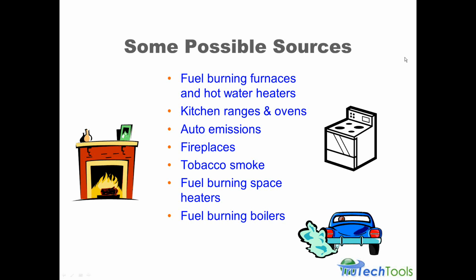Sources of carbon monoxide: don't always assume it's the furnace and hot water heater. There may be other fuel burning appliances, such as natural gas or propane ovens or ranges, even electric ranges, electric ovens especially, if they have a buildup of organic materials. Those are hydrocarbon materials, like somebody's nice blueberry pie that spilled over and burnt and crusted to the bottom of the oven. That can actually burn like carbon. It turns to carbon and can burn like an underfed oxygen situation, where it can also produce CO that has been measured during burners, etc.